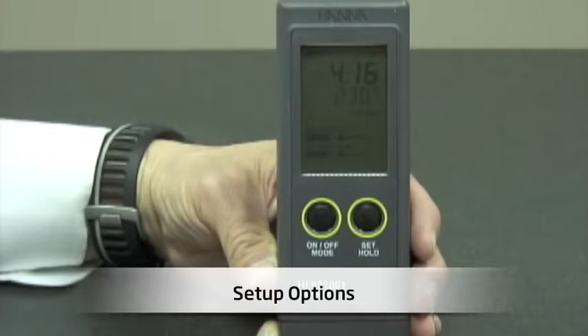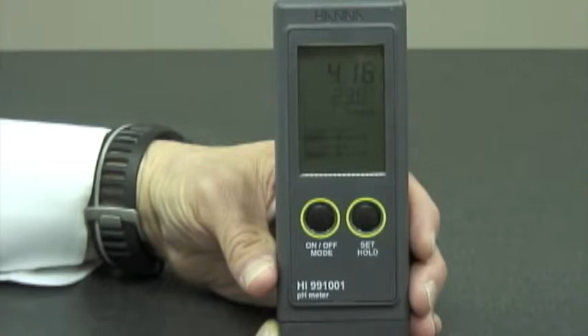Next, I'd like to show you some setup options for the HI991001. Right now my meter is in measurement mode, and what I'm simply going to do is push the left-hand button, and I'm going to hold it down for 6 seconds until it takes me into the temperature mode. At that point, depending on what I want to choose, I can push the right-hand button and choose either Fahrenheit or Celsius by toggling back and forth. Once I have my desired temperature setting, I push the left-hand button, and that's going to allow me to choose my buffer set. In the case here of 6.86, that's going to recognize the buffers of 4, 6.86, and 9.18. In the case of 7.01, that's going to recognize the buffer sets of 4, 7, and 10. So once I choose my temperature settings and my buffer set, I simply push the left-hand button and escape back into the measurement mode.